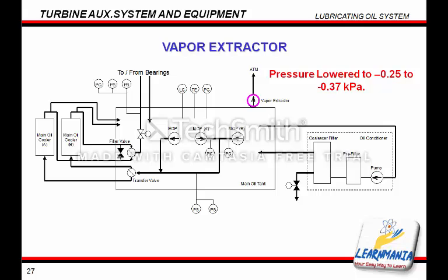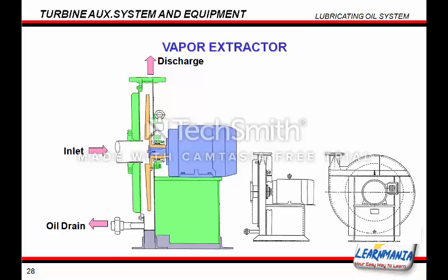The vapour extractor reduces the oil tank pressure from minus 1 to minus 1.5 inches H2O using the valve attached to the suction piping. If the vapour extractor fails, the pressure inside the main oil tank will increase and vapour will leak from the turbine bearings, creating a fire hazard. Thus, Toshiba recommends suspending turbine operation in the event of a vapour extractor failure. The air inlet is located centrally and air discharges from the upper part. Oil collected inside the fan is discharged to the oil tank via the oil drain piping located on the lower section.